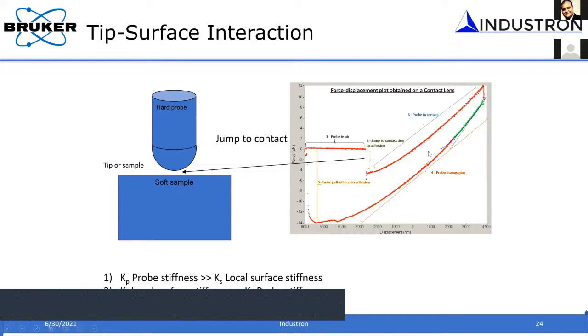Then as you load further, you pass through the adhesion to a repulsive regime, and you start to see this typical load displacement curve. When you unload, you have adhesion between the tip and the sample, and then you have this pull-off. The pull-off gives you a measure of the adhesion between the sample and the tip. This is what you normally get on a soft sample, soft biomaterials. You can't ignore all this interaction and simply assume it is a typical load displacement curve and make a measurement. You will be in error.